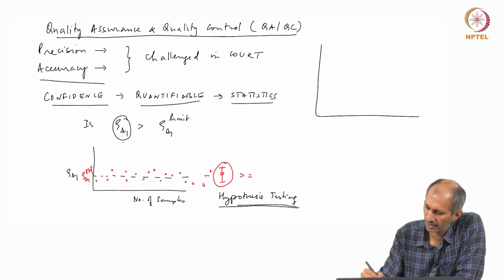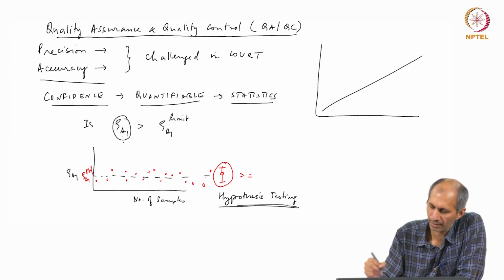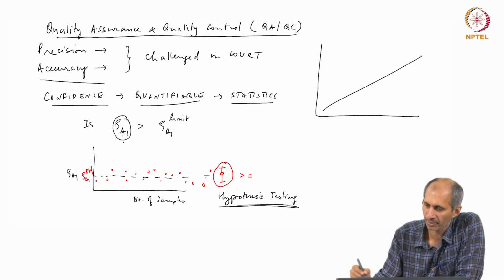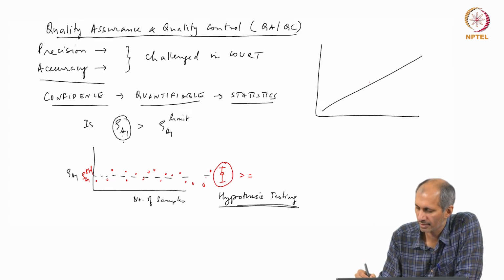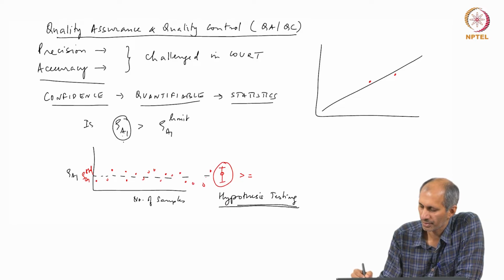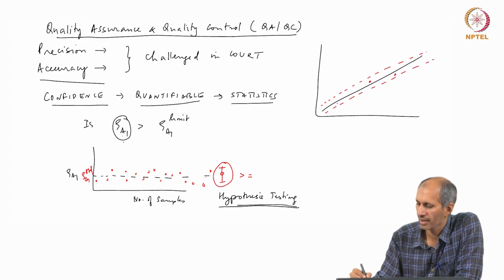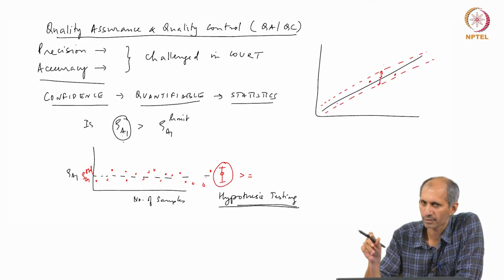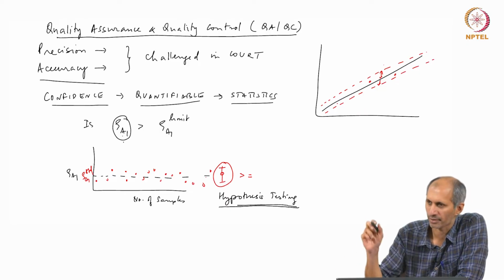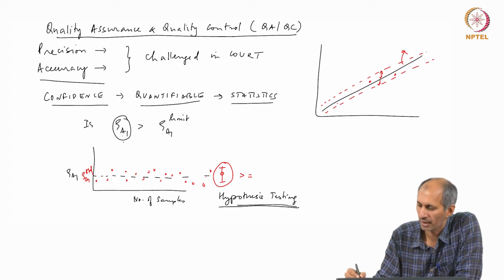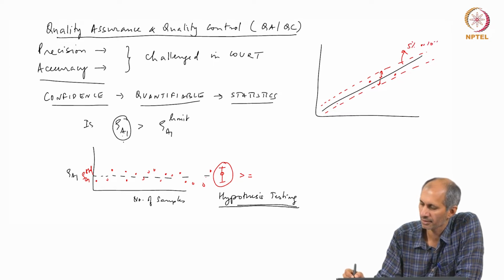So we say calibration, the original calibration is like this, and if the calibration moves, the number that you are getting... this is the original calibration, and every time you open the instrument you run one standard, and the standard is falling here, and the next day your standard is falling here, and so on. So it is not on this line, but somewhere around the line. So you decide that you give some boundary. You say that as long as this is within some percentage of my expected value, I am okay with it, and this number is your choice. I can decide this is 5% or 10% or 50%.